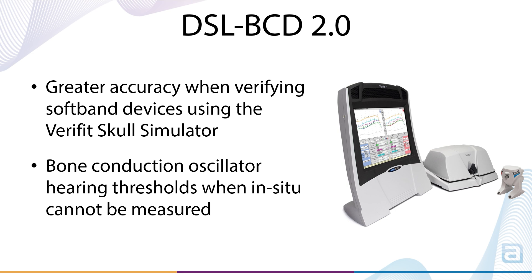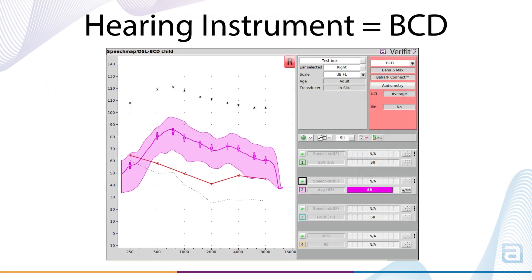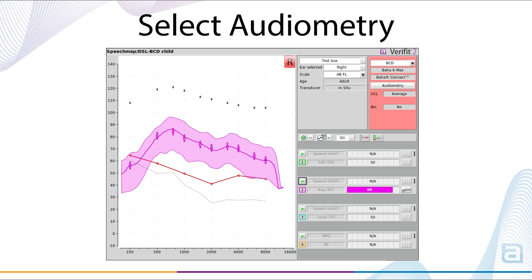This is made possible by a new skin transmission loss correction for children and adults. To access SpeechMap for verifying bone conduction devices using the Verifit Skull Simulator, go to the Hearing Instrument menu and select BCD. This selection was previously labeled BAHD.